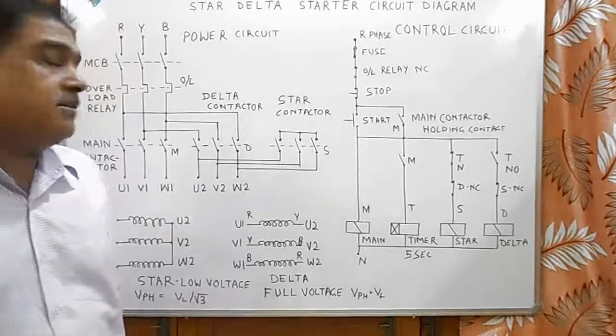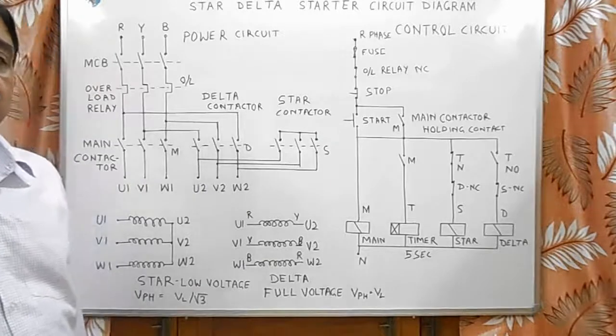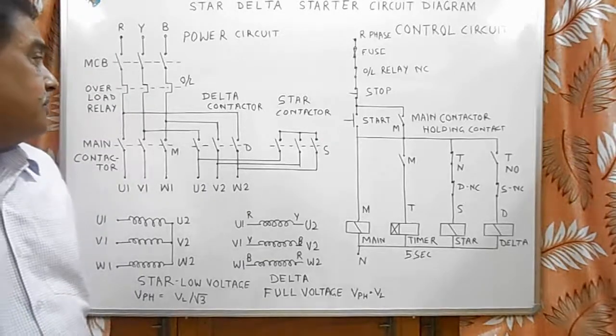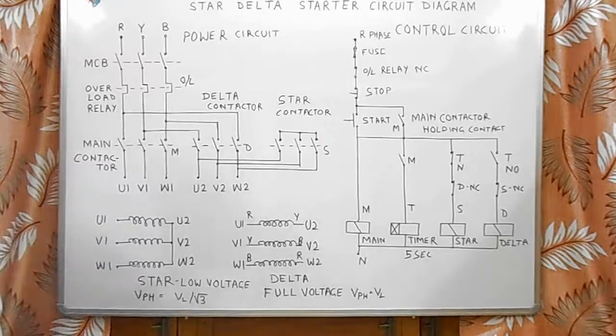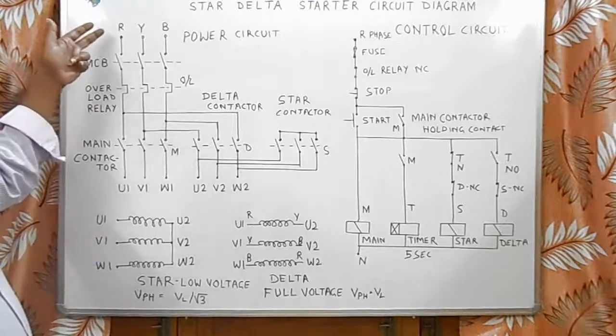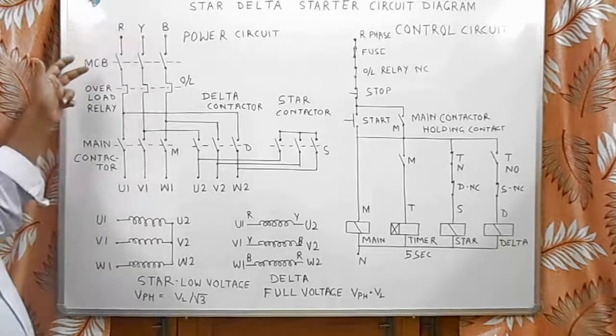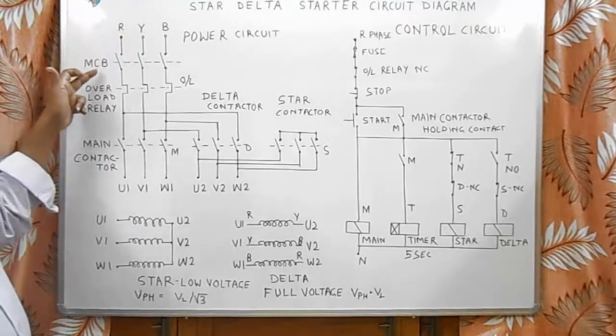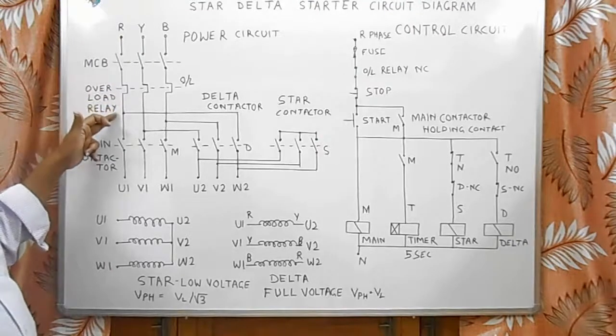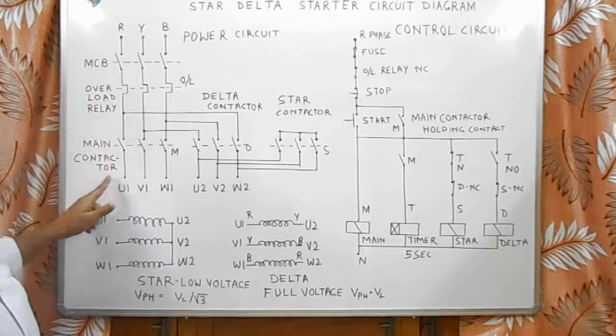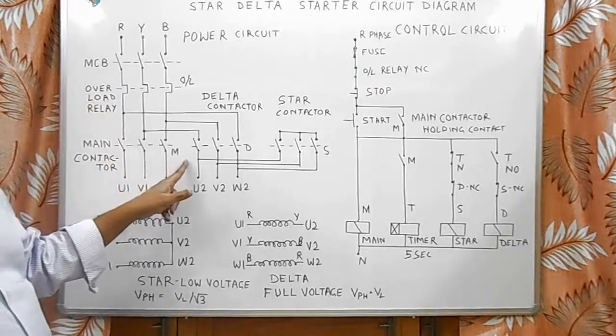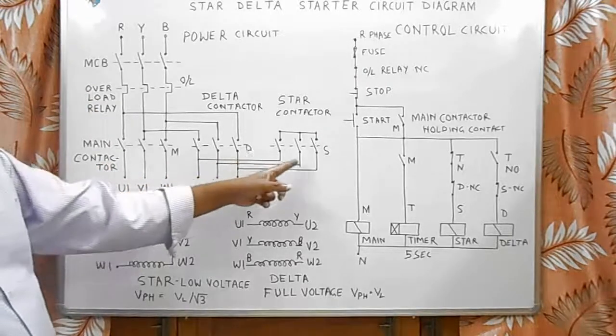In star-delta starter, there are three contactors used. The power supply, three-phase supply received from pole, goes to MCB, from there it goes to overload relay and then it goes to three contactors: main contactor, delta contactor, and star contactor.